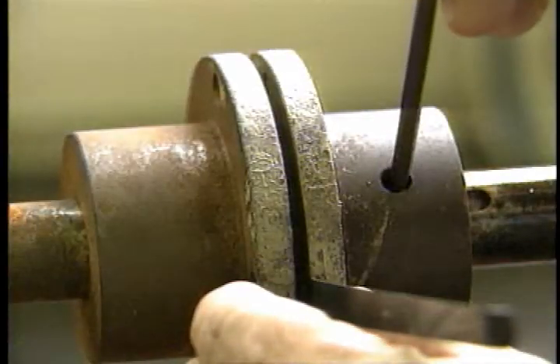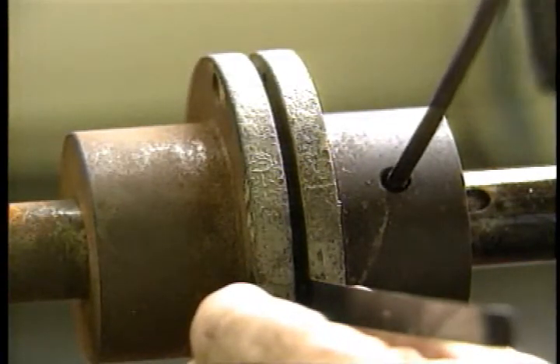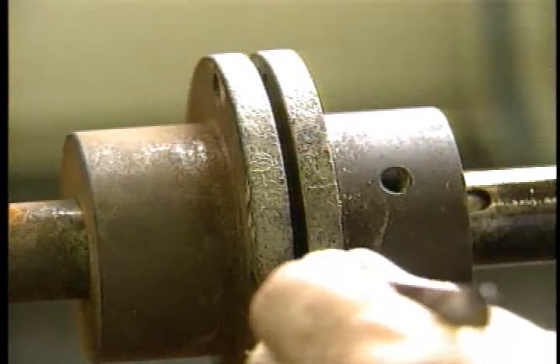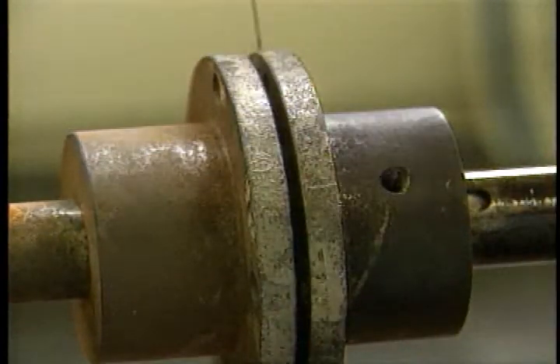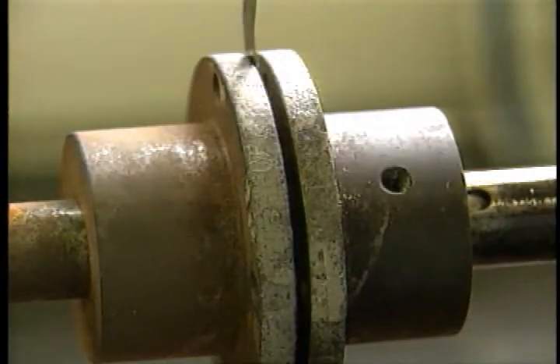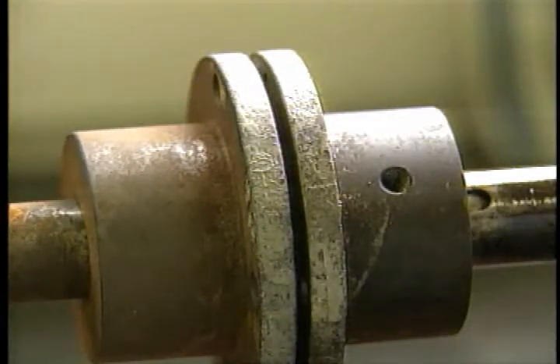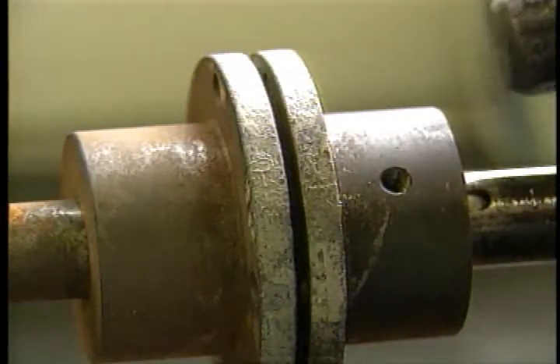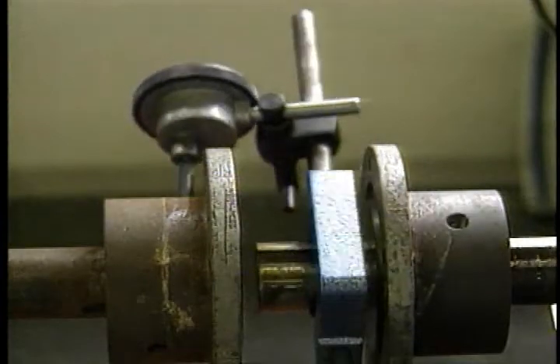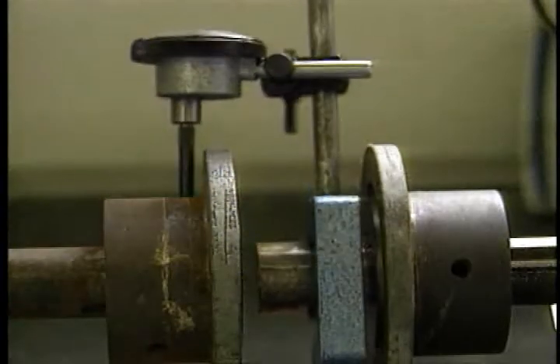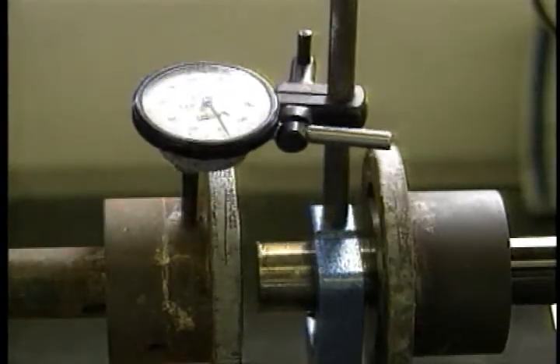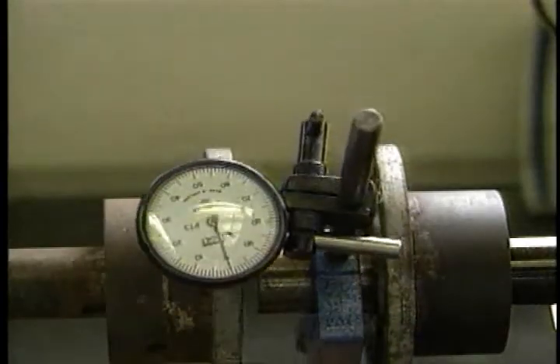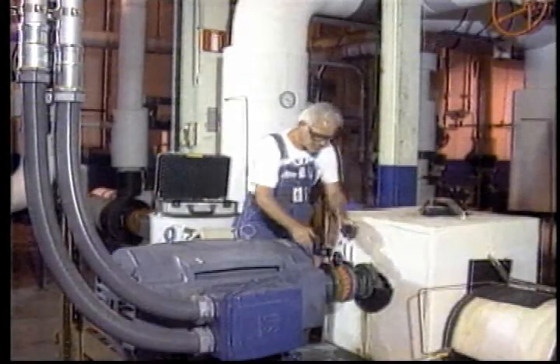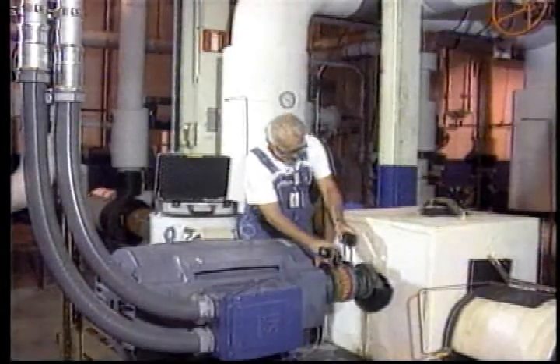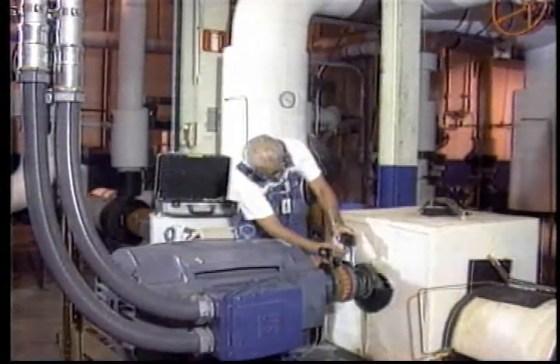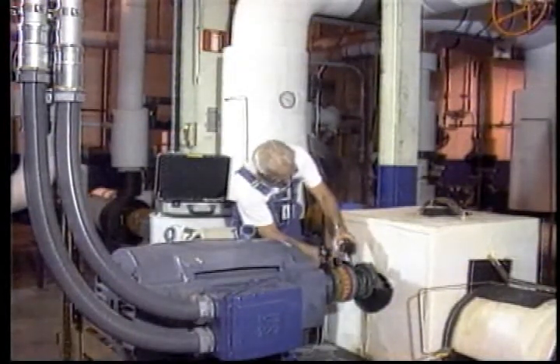To combat misalignment problems, 3 common methods for shaft alignment have been developed. The straight edge and feeler gauge method is the oldest and perhaps still the most common, even though it is the least accurate of the 3 methods. The dial indicator method is more accurate than the straight edge and feeler gauge method, but not as accurate as the laser method. The laser alignment method is the most accurate of the 3 and often requires less than 1/2 the time of the dial indicator method.